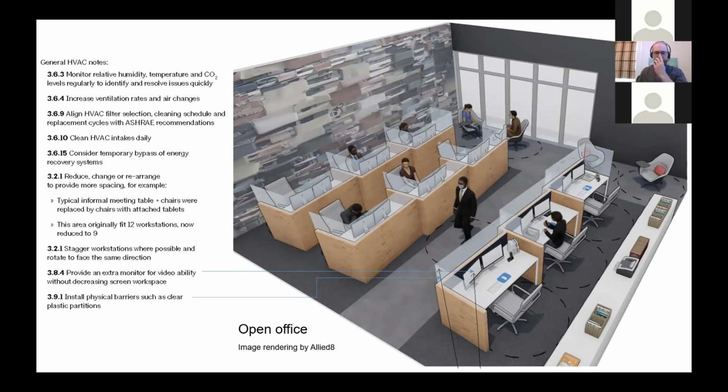And when we gave this presentation with the AIA San Francisco, Les wanted to note that although the desk workers are behind screens, he's echoing what I was just saying. Expect new recommendations that indicate they should all wear masks, even when they're kind of screened off. And ASHRAE indicates that airflow and filtering directly inhibit atmospheric pathogens, and using higher volumes of outside air and at least 6 air changes per hour is desirable.